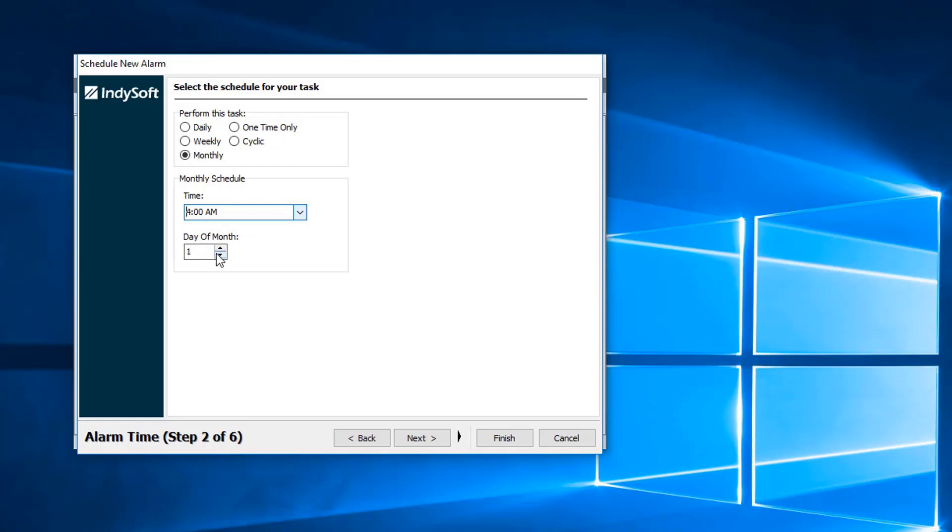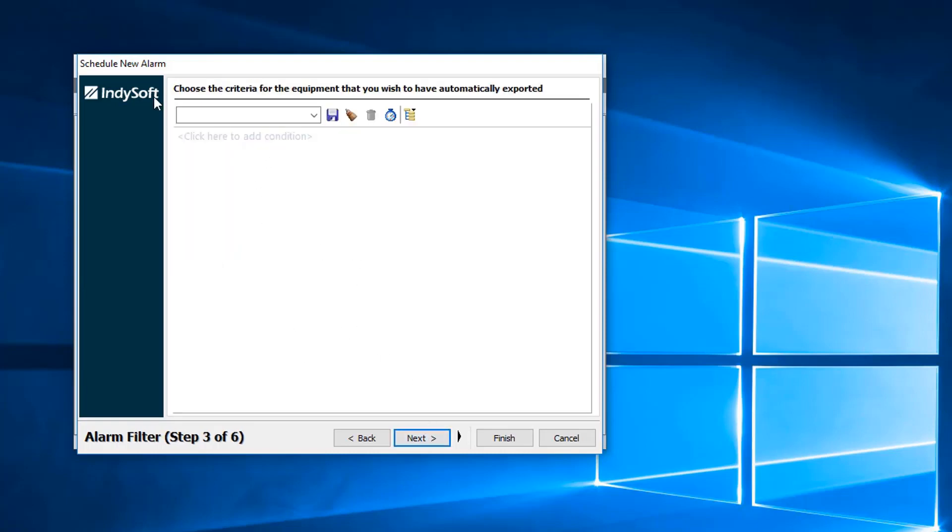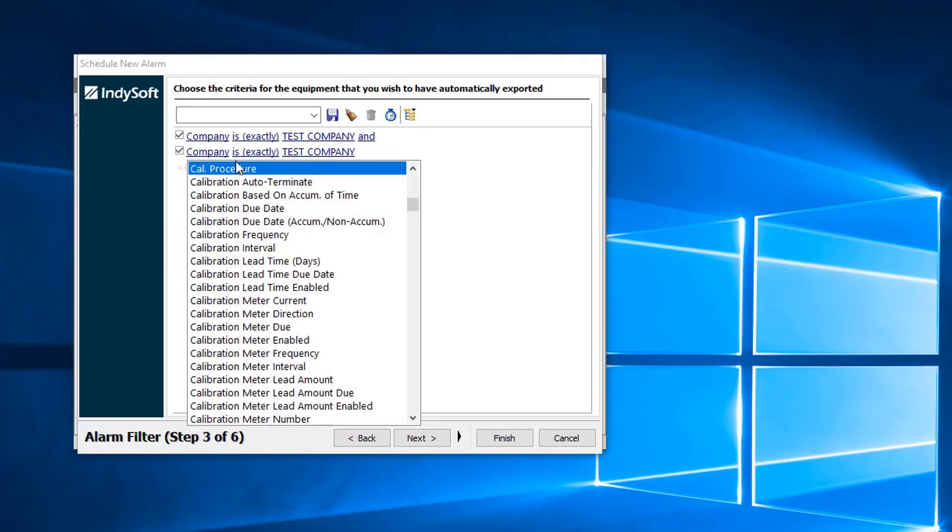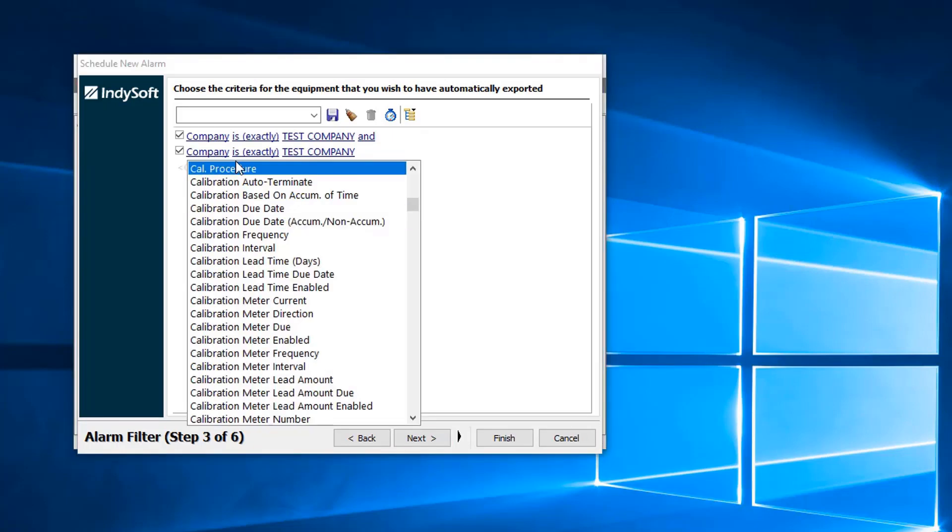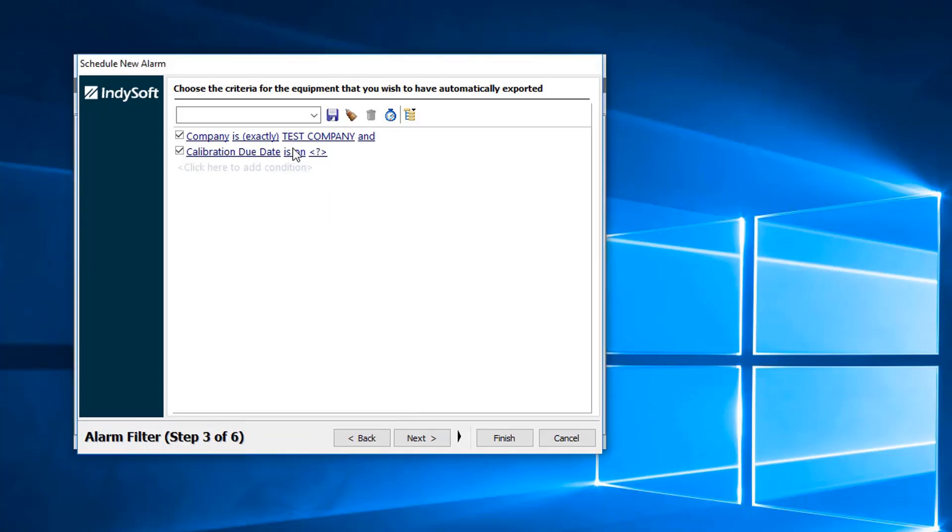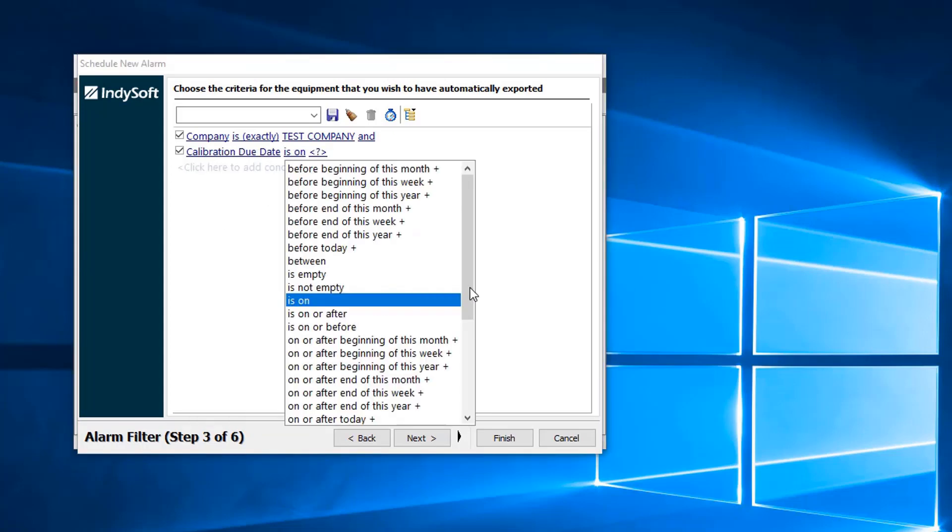And then we can put it at the first of the month or whichever you would like. We then go to next. This is just going to be our filter to choose the criteria for the equipment that you wish to have automatically exported. We could even say calibration due within this month.